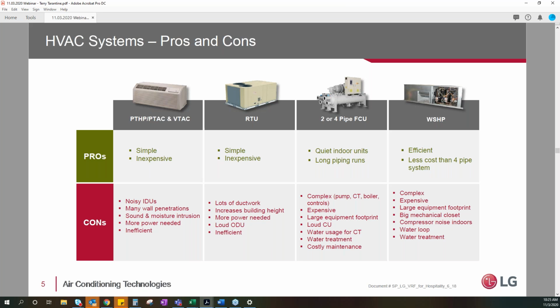Little comparison here. PTAC units, there's nothing simpler than a PTAC unit. They're simple, they're inexpensive. They are expensive to run though. In the typical area, you get what you pay for, and you're looking at energy for a commercial building. Energy is a direct net cost, so you have to make an awful lot of money to recover for the net. They're typically not particularly quiet. In fact, they can be considered noisy. Aesthetics, we've got the wall penetrations going through the building, so there is a sacrifice to the aesthetics of the building, and they are inefficient.